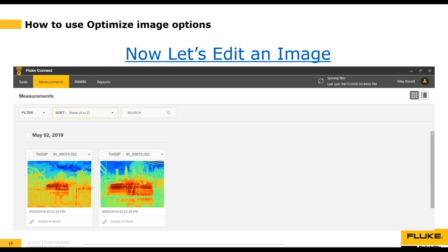What I recommend is: after using your thermal camera to run a maintenance route or do an inspection, copy the thermal image files from your camera to a folder called 'Originals' on your computer — do not touch those files. Then copy those originals into another folder you'll use for editing, and move those files into the Fluke Connect desktop software. Save the original, create a copy, and work with the copy. That way, if anything goes wrong you've still got the original file.